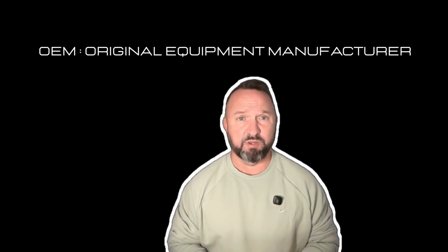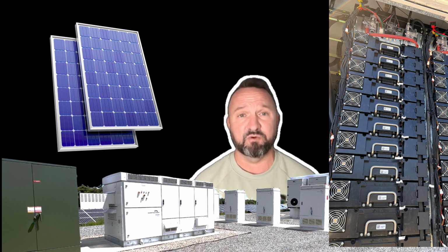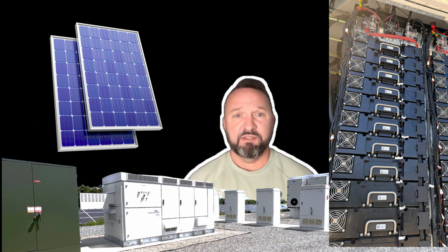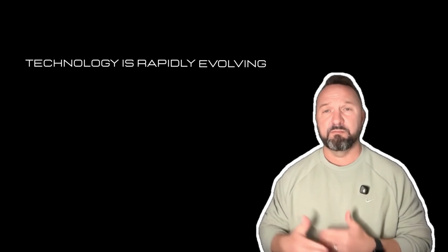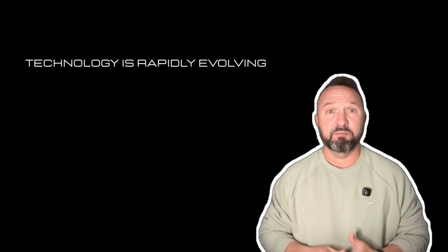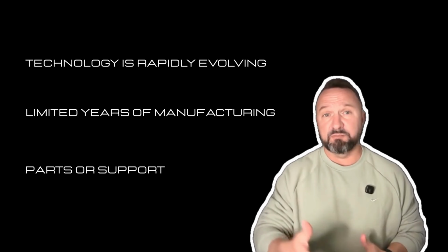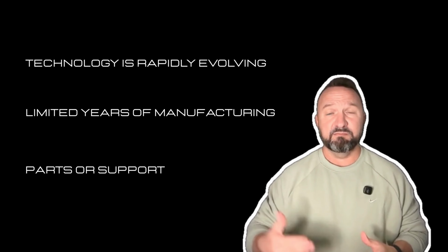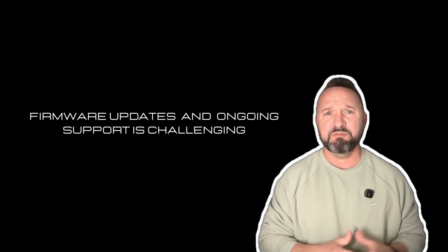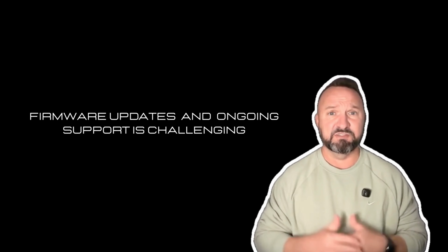So first, OEM, you'll hear that a lot in the industry. It stands for the original equipment manufacturer. When a plant is built, the developer selects specific equipment: the solar modules, the inverters, the battery modules, the control systems, the protection devices, and the transformers or switchgear. Those products usually are manufactured for a limited period of time, and sometimes these manufacturers are releasing new models every couple of years. Not only do they shift makes and models, but the parts no longer are produced to support older models. Sometimes their support or oversight of existing equipment becomes reduced as they focus on new products, and the firmware updates either stop or reduce in frequency. And so replacement components disappear from the market, making operations that much more challenging.